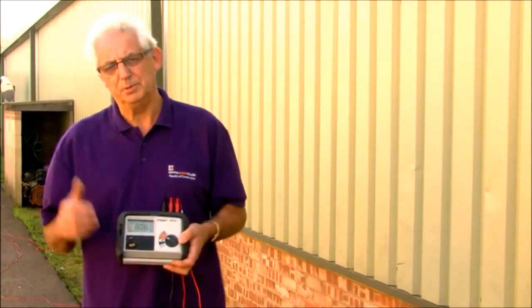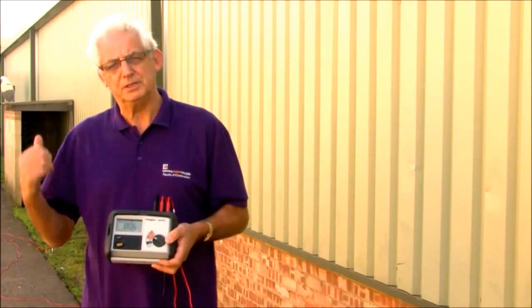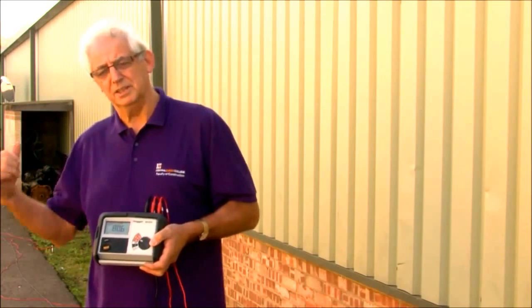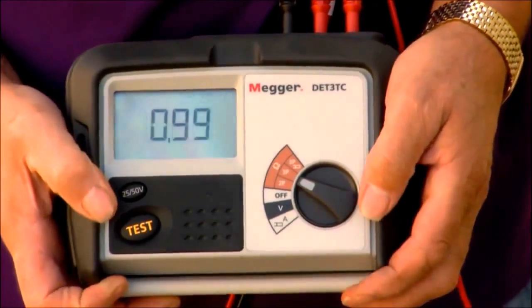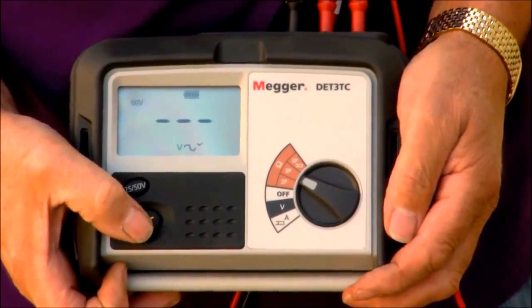Now I need to move the potential electrode 2 meters nearer from the center to the current electrode. I've now moved the potential electrode 2 meters from center nearer to the current electrode, and I need to take a third test. I've got a value of 80.7. What I need to do now is add all 3 values together, divide them by 3 to find the average, and that would be the value I wrote down.